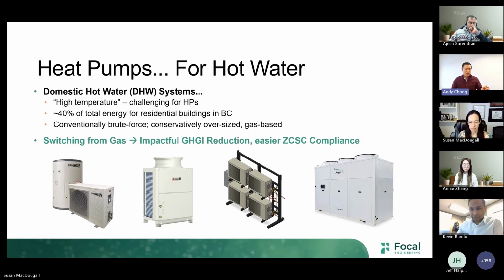What I love about applying heat pumps for hot water is we already tend to have centralized hot water systems outside of people's suites. Whether building new or retrofitting, we don't need to mess about in residential areas—no impact to ceiling heights, suite finishes, fixture types, or noise in the units, unlike heating, cooling and ventilation systems. This is stuff tucked away in a mechanical room or relegated to the roof. Switching domestic hot water production from what's conventionally been de facto natural gas is one of the most impactful ways we can reduce greenhouse gas emissions. In some cases we can reach higher steps of the zero carbon step code without doing much more on the heating and ventilation side.